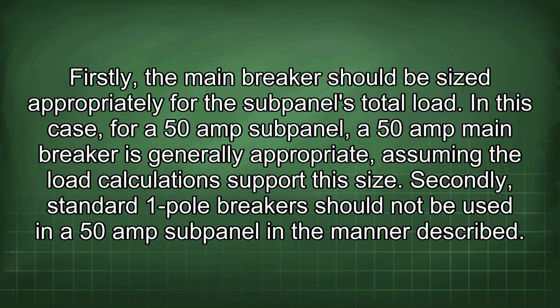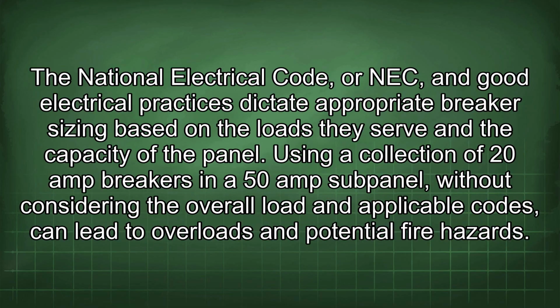Firstly, the main breaker should be sized appropriately for the subpanel's total load. In this case, for a 50-amp subpanel, a 50-amp main breaker is generally appropriate, assuming the load calculations support this size. Secondly, standard 1-pole breakers should not be used in a 50-amp subpanel in the manner described. The National Electrical Code, or NEC, and good electrical practices dictate appropriate breaker sizing based on the loads they serve and the capacity of the panel. Using a collection of 20-amp breakers in a 50-amp subpanel without considering the overall load and applicable codes can lead to overloads and potential fire hazards.